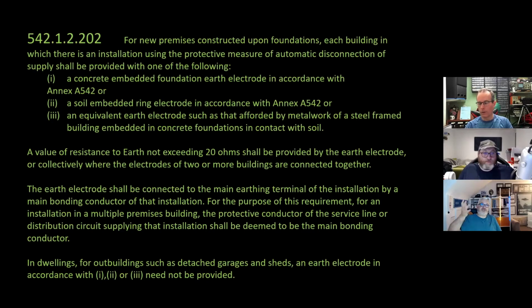Now, just for everyone wondering why an earth bonding conductor, it's because this is about managing that rise in potential for STEP. This isn't about earthing the fixed installation, because when I first saw this, I thought this is by definition an earthing conductor connecting the fixed installation in. No, it's not about that. It's about equalizing step voltages and stuff. Yeah, so it's like a bonding conductor to earth. Yes, because there's an earth there.